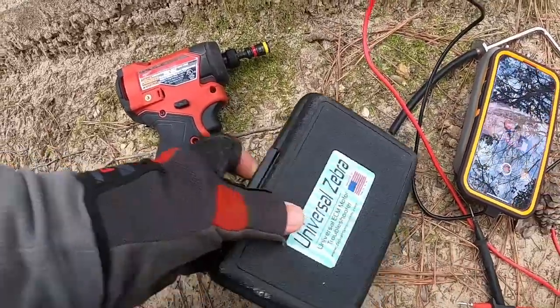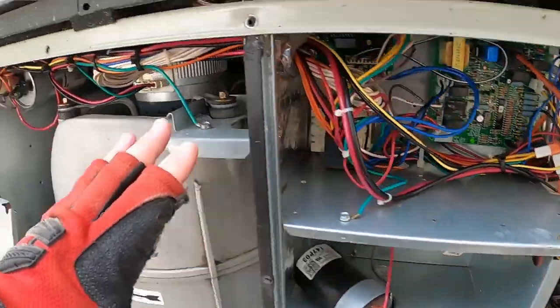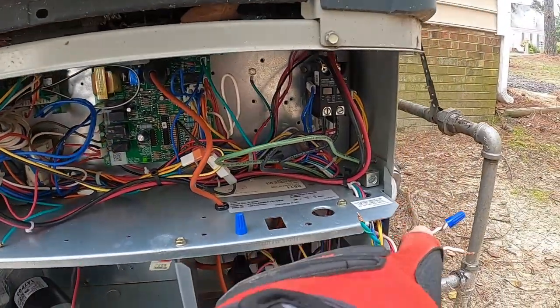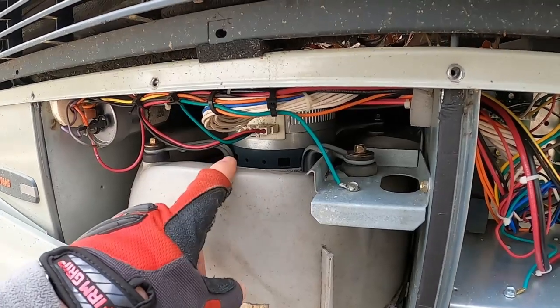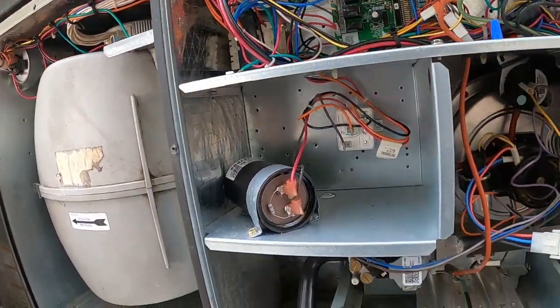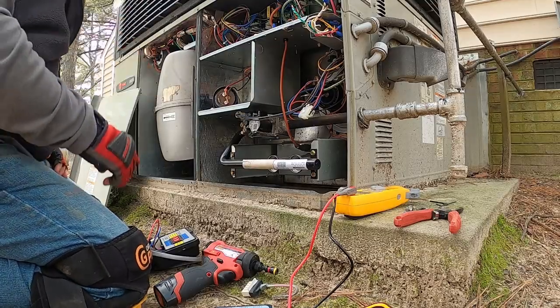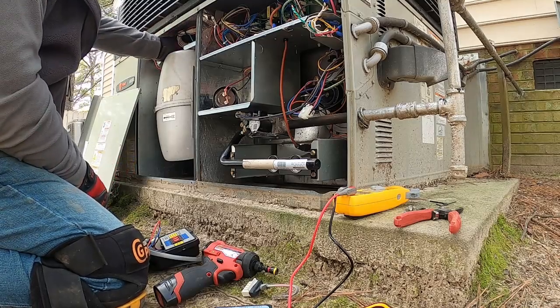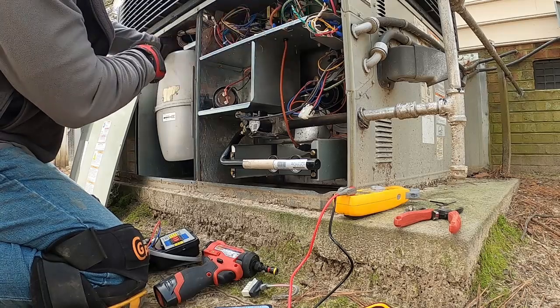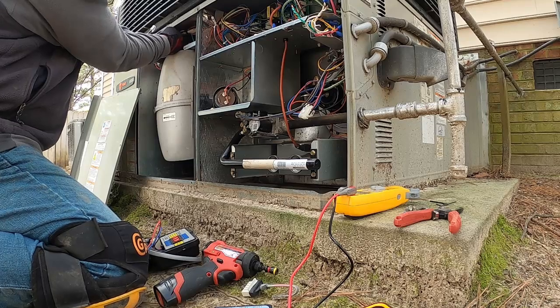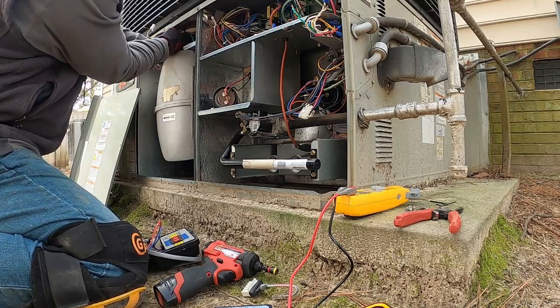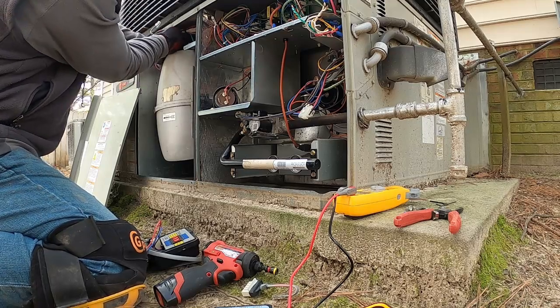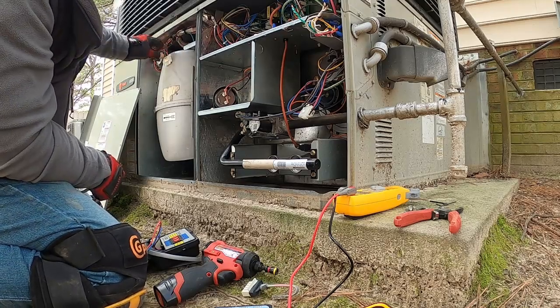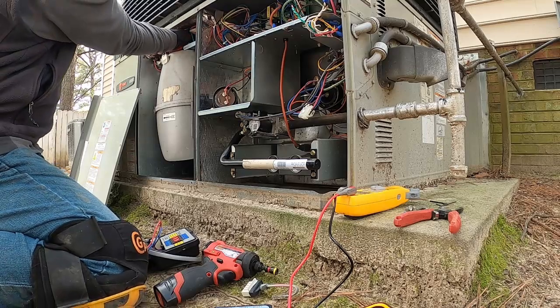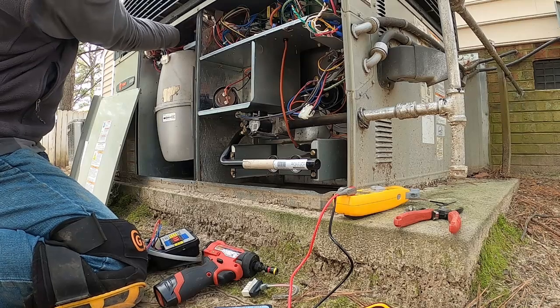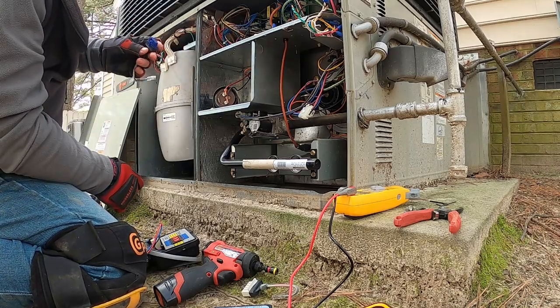So now I'm gonna hook up this zebra tester real quick and we're gonna test this motor, see if it's the board or the motor, because I don't want to assume that the board is causing this problem without actually testing this motor first, because it could be the module. So let's check that real quick. Like I said, I don't want to assume that this board is causing that problem and the blower problem. Come back, put a board in it and put a heat exchanger in it, if that's what he decides to do, and then you get it turned on and the blower don't work. So then you're looking at another problem. So I want to confirm, does he just need a board and a heat exchanger, or does he need a board, a heat exchanger, and a blower module?